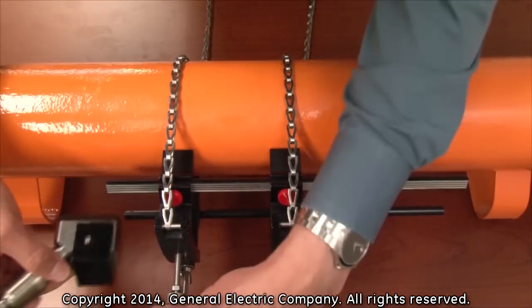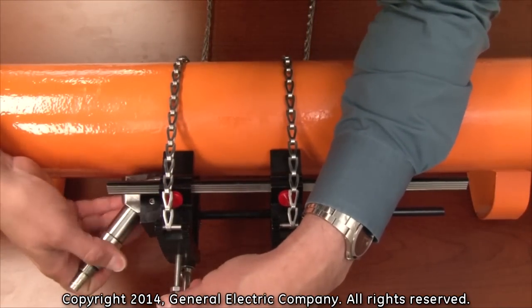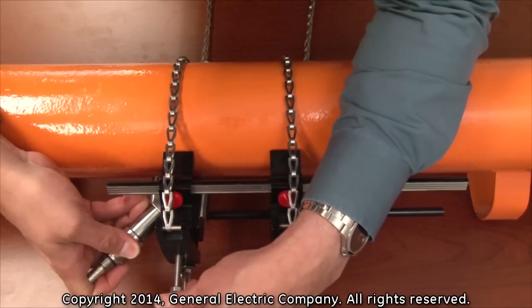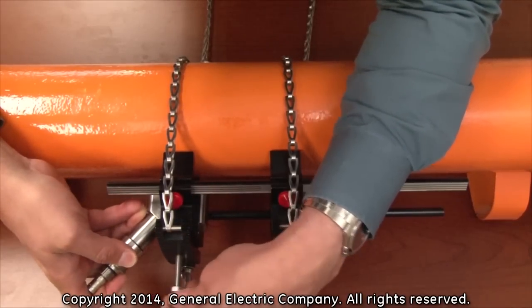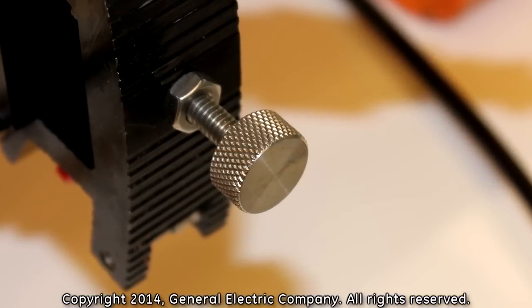For the installation, slide the transducer into the mounting fixture and ensure that the center bolt fits into the insert hole on the top of the transducer securing bracket. Make sure to orient each transducer toward each other so that the BNC connections on the other end of the transducers are facing outward.